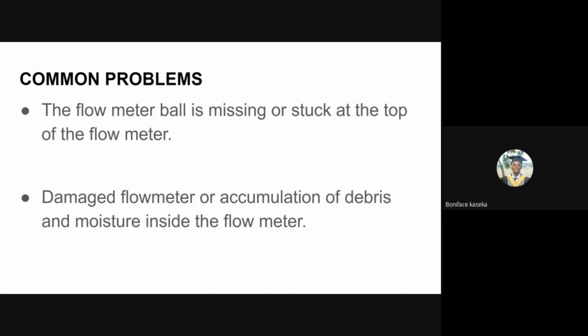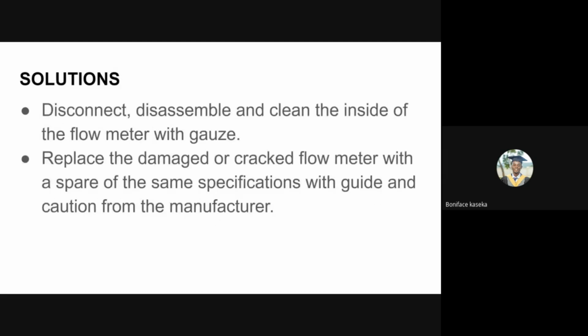So we're going to talk about some of the possible solutions when you have encountered this problem. The first solution is to disconnect, disassemble, and clean the inside of the flow meter with gauze. This is simply to remove the dust and the moisture, and as a result, to decrease the friction. In the case of a cracked flow meter, just make sure that you have a spare flow meter and you replace it, but also make sure that the specifications are in line with the manufacturer's guide. So you need to check with the manufacturer for that particular model and make sure that the flow meter you are using is compatible with it.